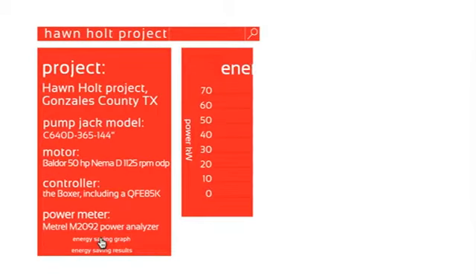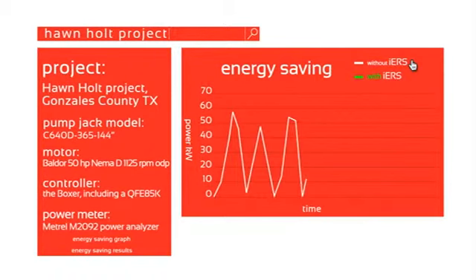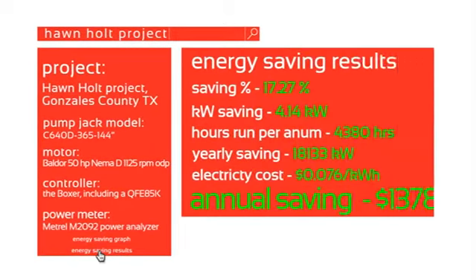This graph shows the energy consumption over four cycles. Each cycle took approximately seven seconds. The white line shows the normal energy consumption and the green line shows the energy consumption when the IERS was turned on. Comparing only the four cycles, the energy saving was found to be 22%. The next test was to run the pump jack for 30 minutes without any energy saving and then 30 minutes with the IERS energy saving system turned on. The overall energy savings were found to be 17.27% and the amount of energy saved was 4.14 kilowatts.